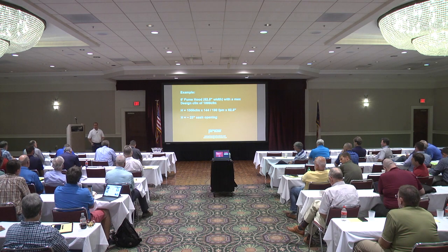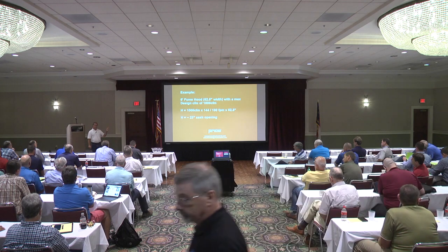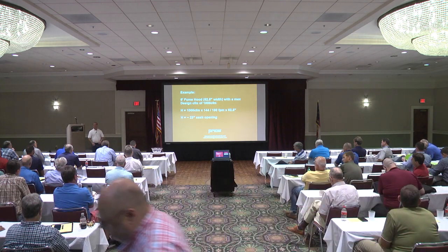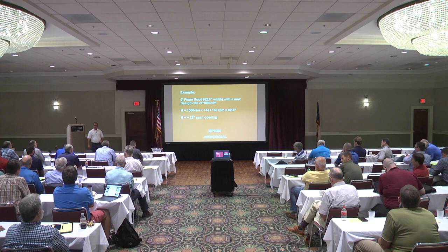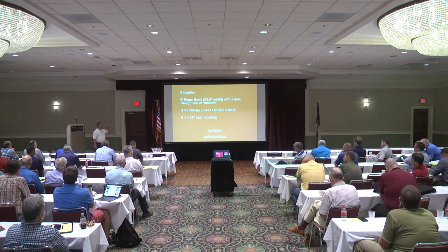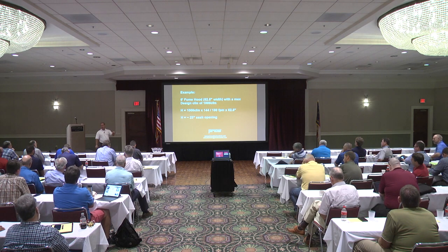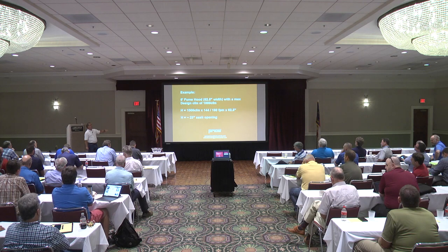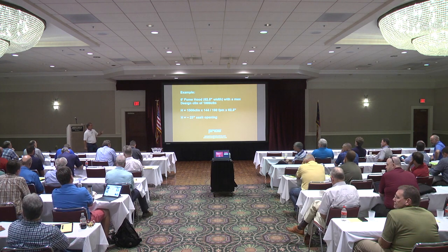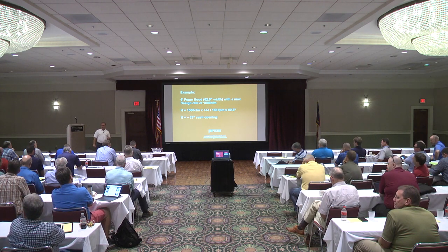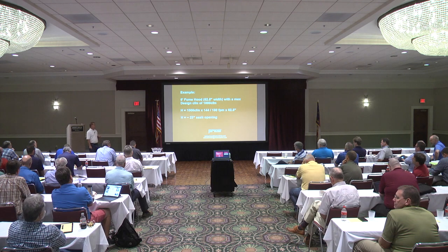If there could be an energy concern, there could be a sash height concern, there could be many things. We all know in the heat of battle, trying to deliver a job that's already 6 months behind, we're probably not going to want to be taking the effort to write RFIs. But this is how you're going to figure out the sash height associated with these known parameters that are part of the contract documents. Let's leave it at that. The 100 feet per minute is specified and the 1,000 CFM is specified. And that's how you're going to get to that point.